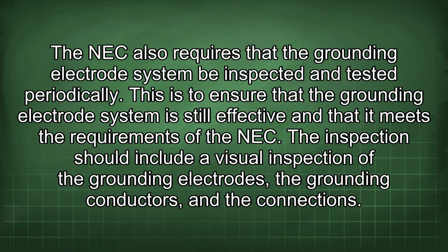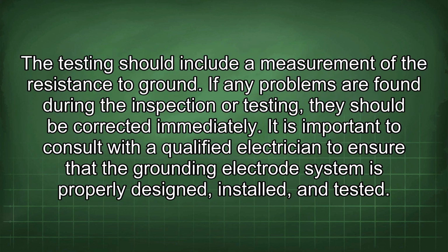The NEC also requires that the grounding electrode system be inspected and tested periodically. This is to ensure that the grounding electrode system is still effective and that it meets the requirements of the NEC. The inspection should include a visual inspection of the grounding electrodes, the grounding conductors, and the connections. The testing should include a measurement of the resistance to ground. If any problems are found during the inspection or testing, they should be corrected immediately.